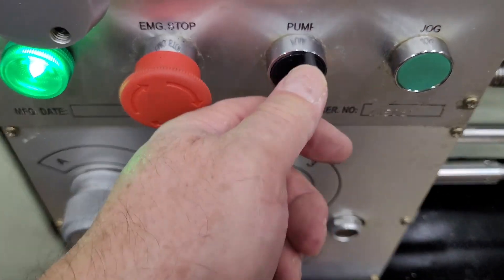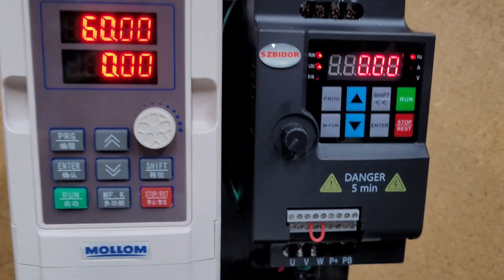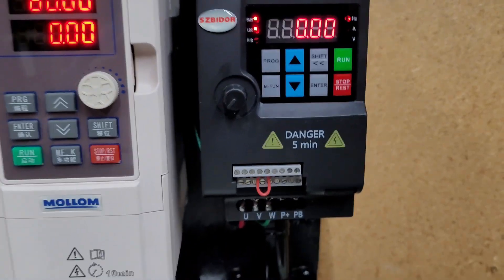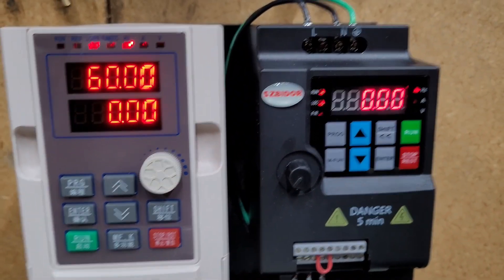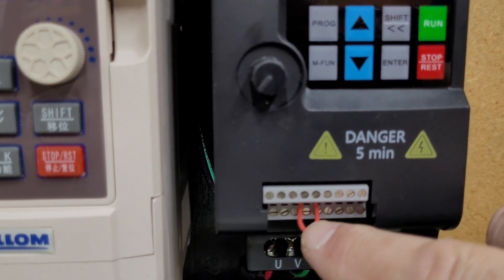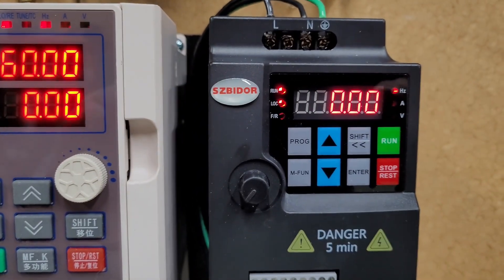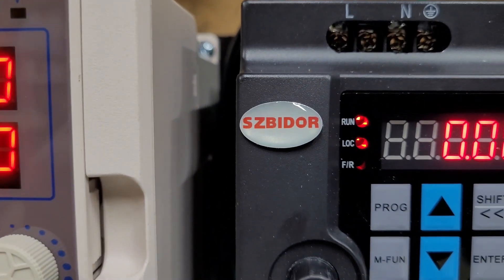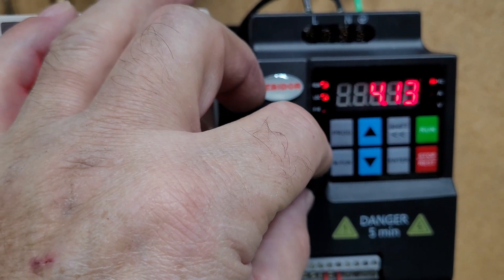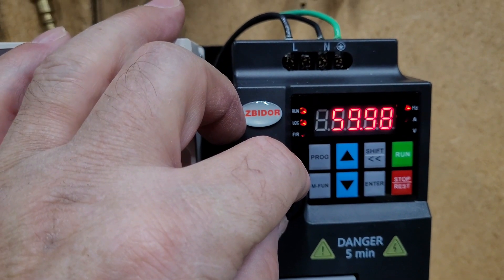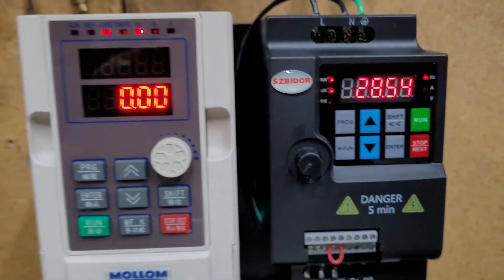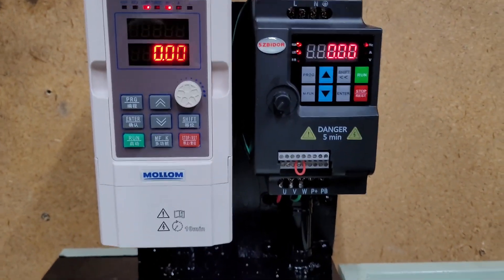The coolant pump is set from this, so I'll just turn that on. The second VFD comes up, and it controls the coolant pump only. The fan is on because it's set through this digital connection here - digital input 1 to ground. When that's shorted and the unit's programmed to do so, it's in run mode right now. I just rely on the potentiometer here to set what frequency I want. I tend to leave it at zero - it'll go all the way up to 60 hertz. I tend to keep it at zero just because I can control the coolant flow better. So that's how the VFDs function.